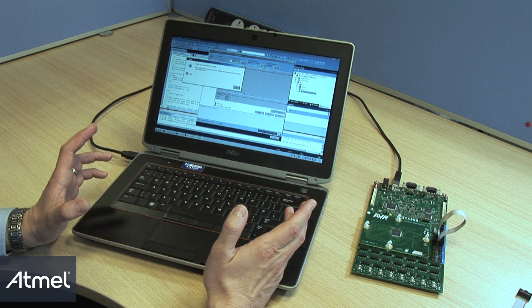Now what I'll do is disable those two. Once we do this, we program these settings to the target device, and shortly after we already get an error message back. The icons have changed to a warning sign, and if we click on read now, we get an error message back, so we cannot communicate with the target board via our JTAG interface.